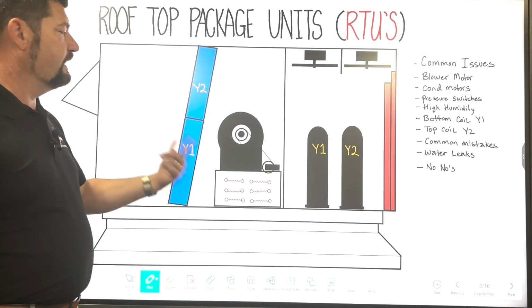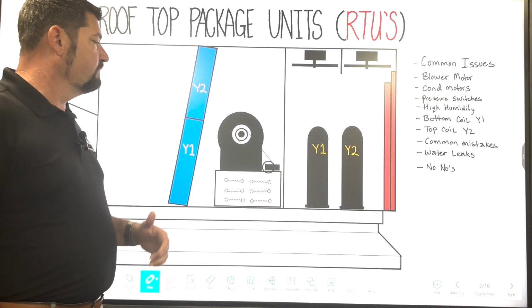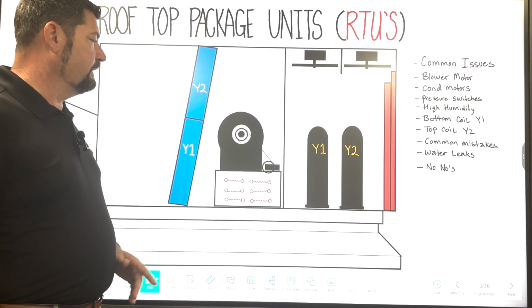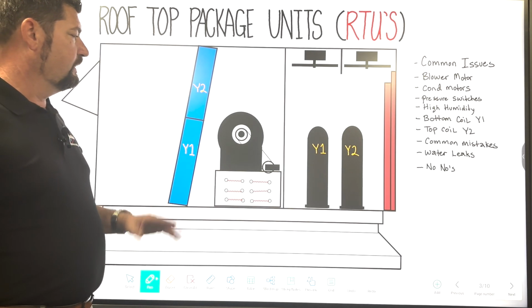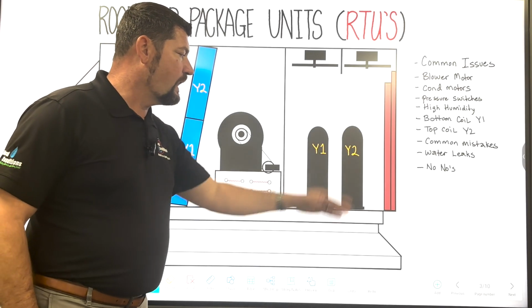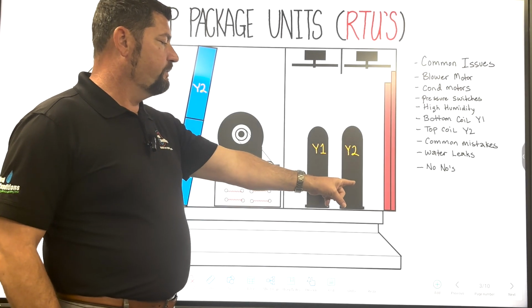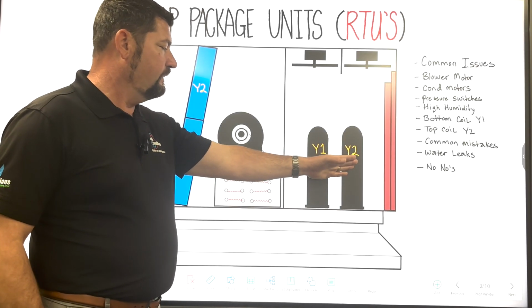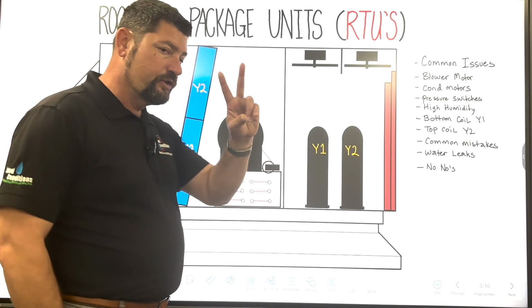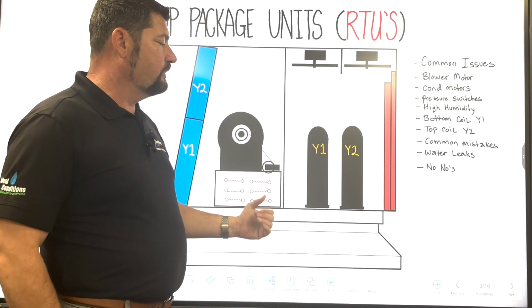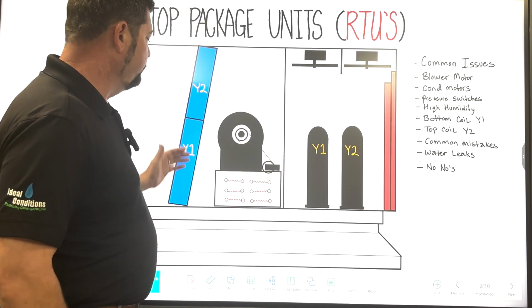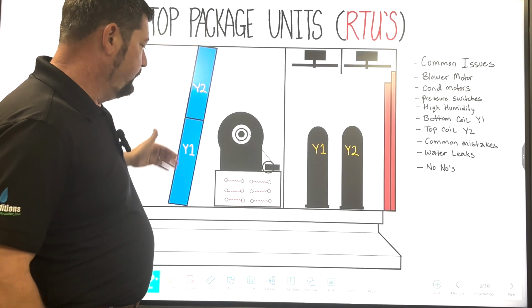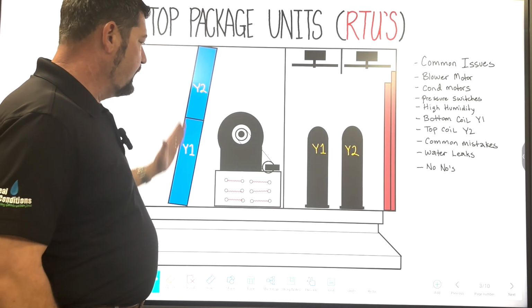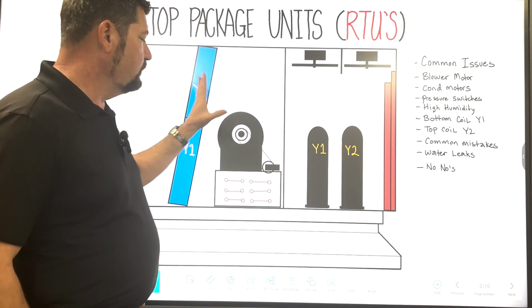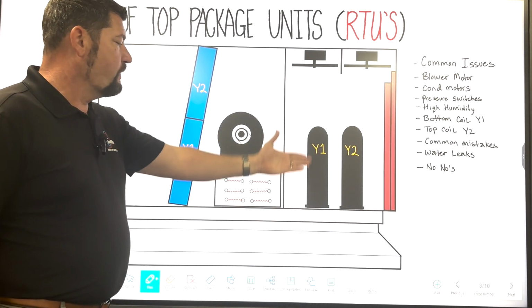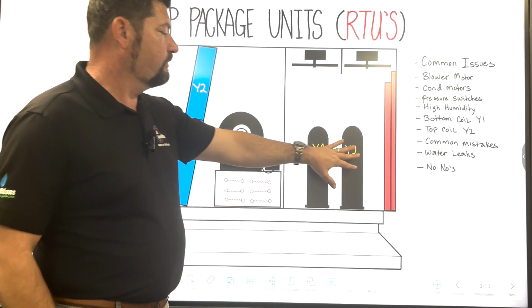So you're not really dehumidifying there. If there's a humidity issue, check and make sure that both circuits are running. In the event that it's just out of sequence and you have your Y2 compressor as your main compressor, and that one's coming on and the Y1 compressor, you have that as your Y2, and it doesn't come on until you have a high demand, then having these coils backwards as far as the sequence goes would put that humidity back in there too.